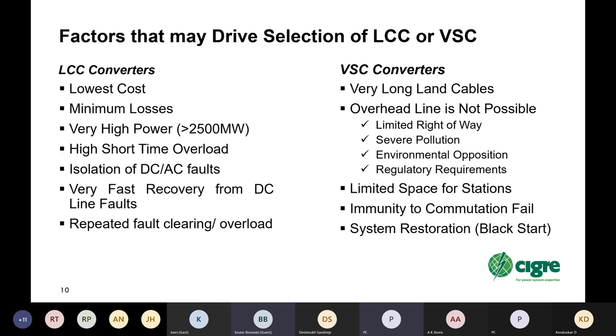VSC converters are also relatively immune to commutation failure and can ride through events that would basically cause a complete interruption of an LCC power transfer, and the VSC might still be able to transmit some power through, for instance, single line to ground faults, whereas with an LCC, the power transfer is not very high at all. And of course, as already mentioned earlier, VSC gives you the possibility of system restoration because it has black start capability, which is very difficult to do with LCC, unless you provide synchronous condensers and other very specialized equipment to allow a restoration or a startup in a black system.